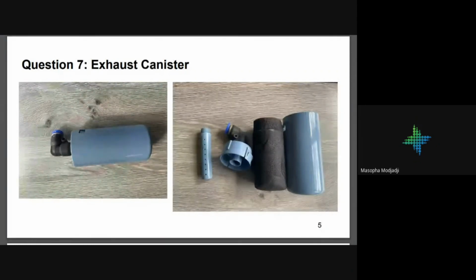Here is what you need to do to solve the problem. You will need to open the exhaust canister as shown in the picture. That is the exhaust canister. And then you will need to take out the sponge and clean. Also, disassemble the part with a tube that has pores. Remove the zeolite in that tube and unblock all the pores clogged by the zeolite. Once this is done, the machine should be able to produce good oxygen levels.